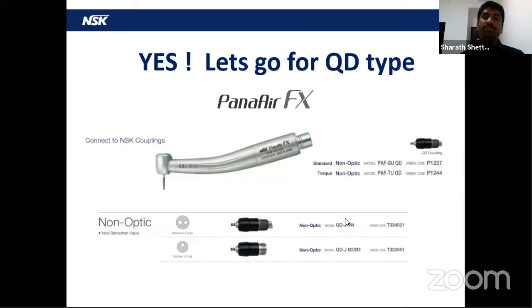That means you just need to go for the QD type. So next time when you're purchasing a handpiece, you can insist or inquire if they have this QD type of handpiece. Now, what is this QD type? It's exactly the same handpiece, but with a different shape, and it comes with a coupling, that is a QD coupling. Now you clearly understand the use of this coupling, because this coupling has the non-retraction valve. The clean head system is already there in the handpiece, just the non-retraction valve will be there in the coupling. So once you purchase this set, the handpiece as well as the coupling, your handpiece gets the protection of the non-retraction valve as well as the clean head system.